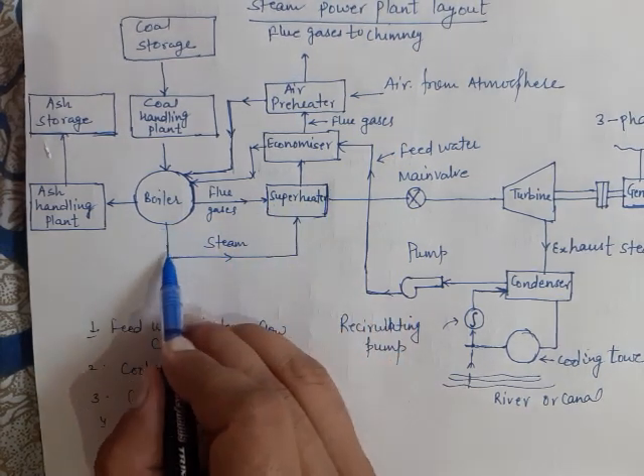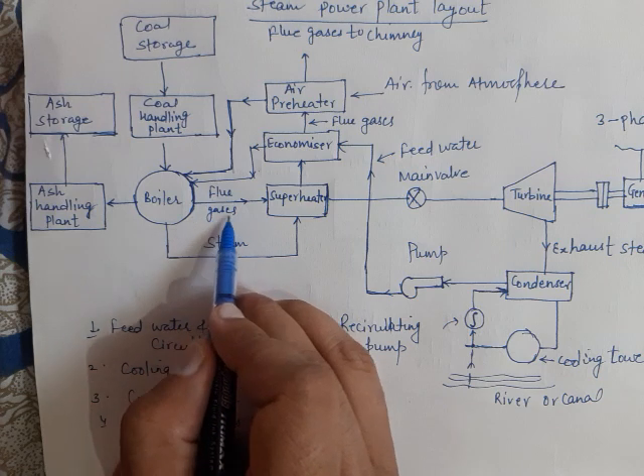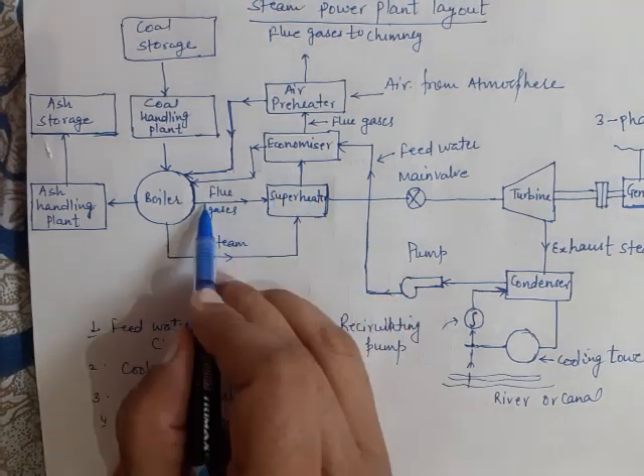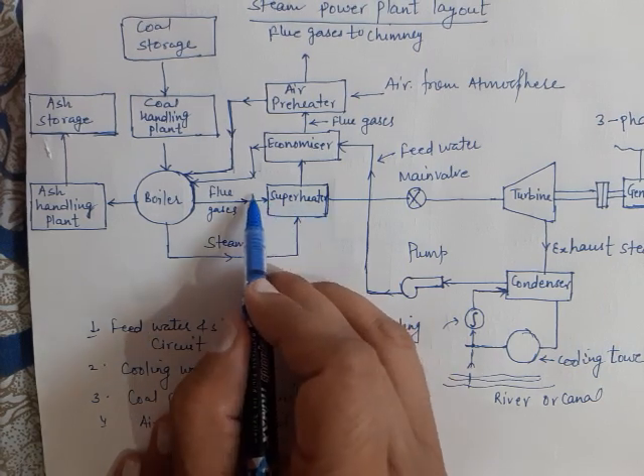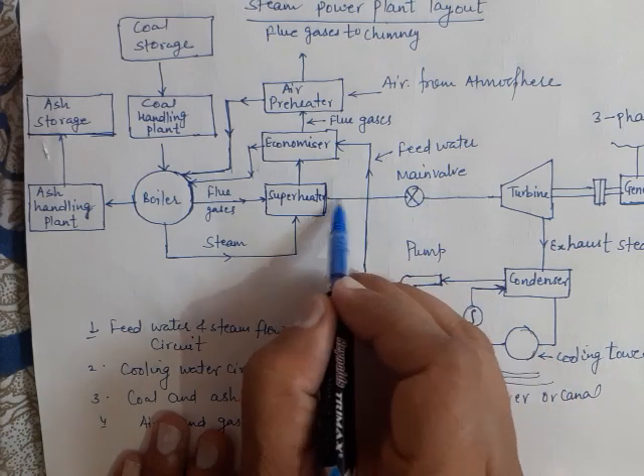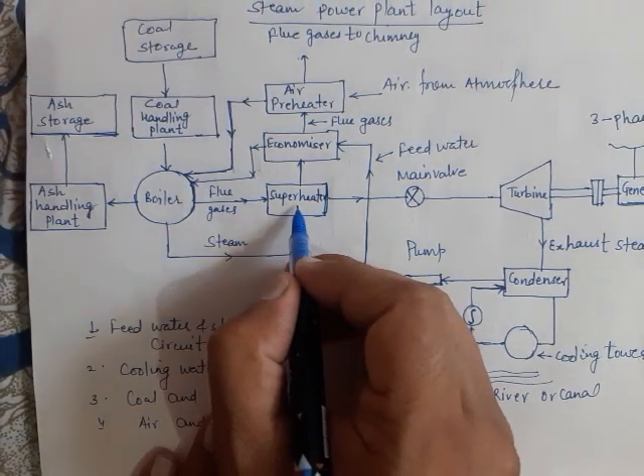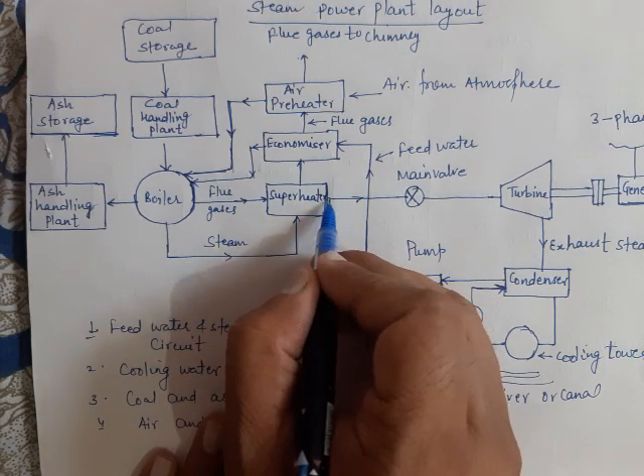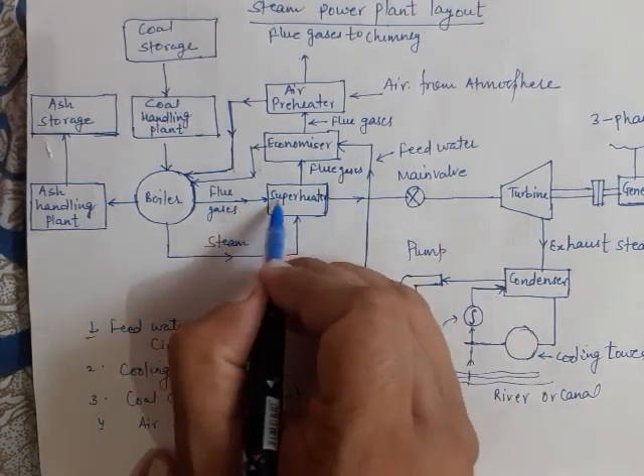The flue gases generated in the boiler are sent into the superheater, where the steam coming out of the boiler is superheated. The hot flue gases, as a result of combustion of fuel, flow through the superheater, then through the economizer, and then through the air preheater, before being discharged to the atmosphere via a chimney. This is the flue gas circuit.